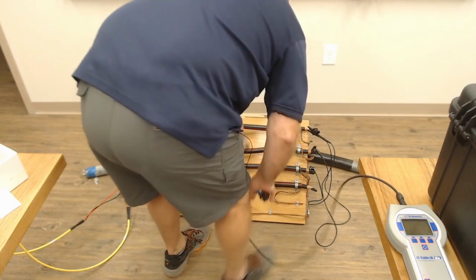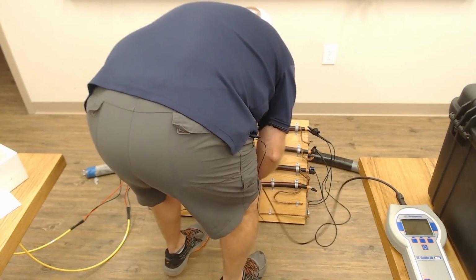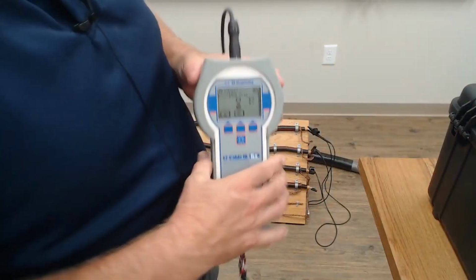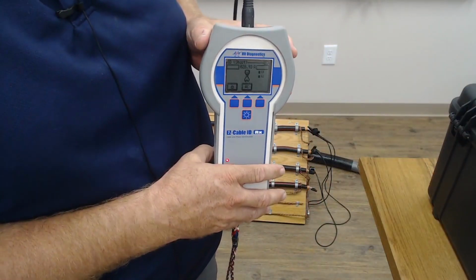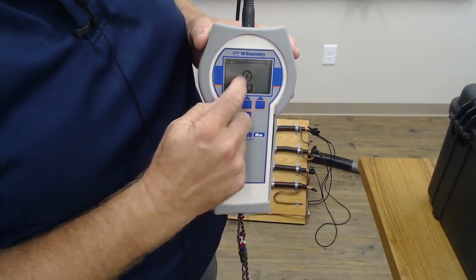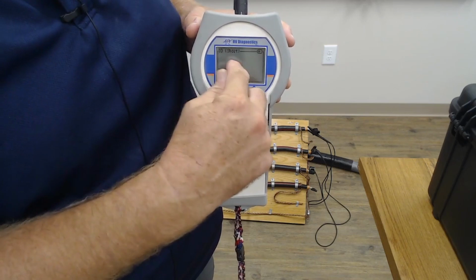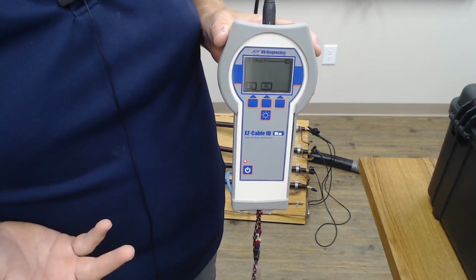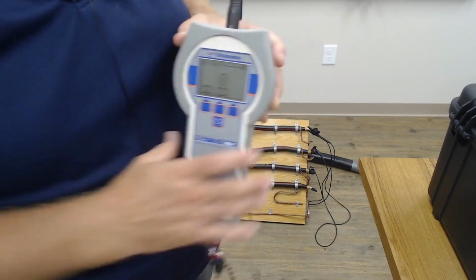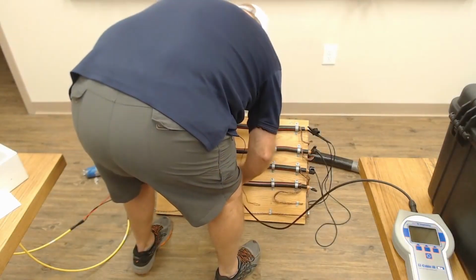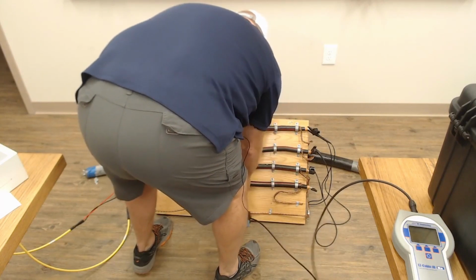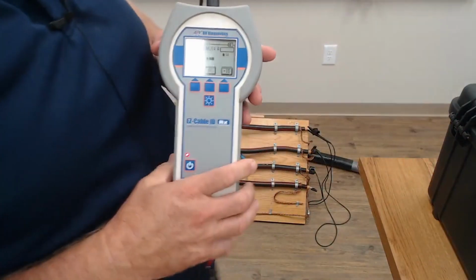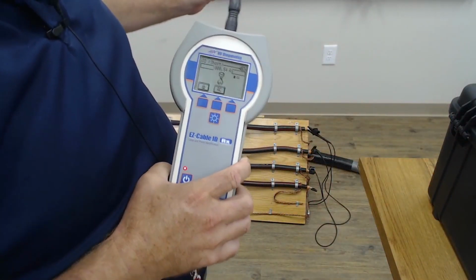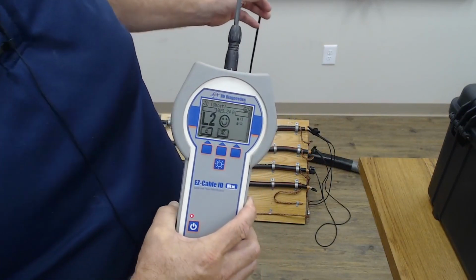Likewise, if we go down to the wrong cable, that symbol there says can't find signal. There's a pulse there with an arrow through it, means that is not a valid signal. That's what is showing there. Let's go to another cable. Hopefully this is L2. There we go, L2 smiley face.